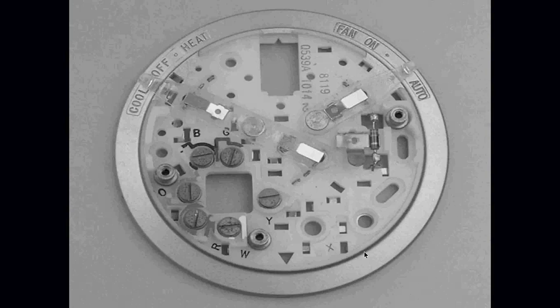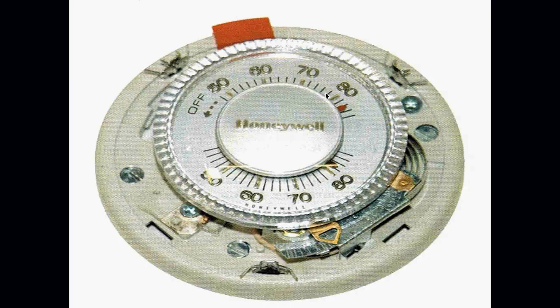Another type, which is much more frequently seen still to this day in houses, is the round thermostats. Okay, these are the little ones that are on the wall that are usually either off-white or silver in color, and they're round and you twist them. Okay, we have our wiring connections right here on the subbase. We have our switching on the subbase. Okay, and our thermostat mounts right onto this subbase. Okay, and again, these are important to be level because this style of subbase, unless it's a digital round thermostat, has mercury in it. Okay, we don't see a ton of that anymore because as we've been replacing these round thermostats, we've been replacing them with digital.